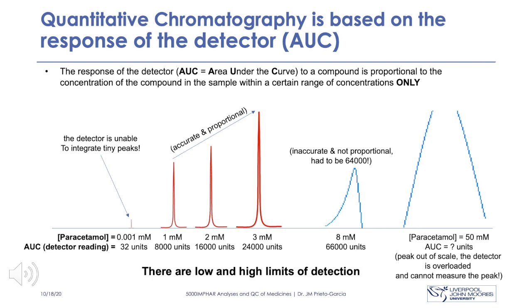This is inaccurate and not proportional. The machine gives us 66,000 units, but actually if it was proportional according to the previous ratios, it should be around 64,000. Finally, if we inject way too much, the peak goes out of scale and the detector is totally overloaded and it cannot measure the peak because it doesn't know how high it goes. So, we have to be careful and know very well our machines, as to know where we have to dilute the sample or not, to get the injection within the accurate and proportional detection limits of the machine.